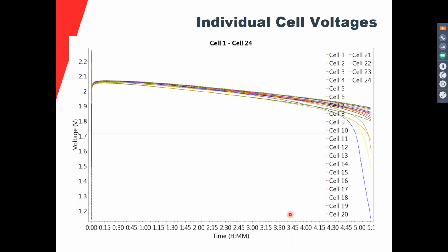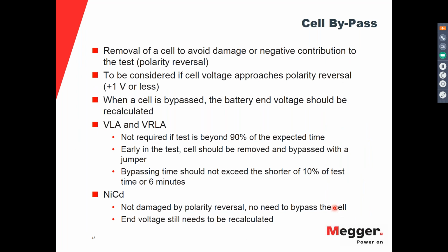And here we have another example, and this is a more critical example. You can see that there are three or four cells that are having serious issues, dropping the voltage very fast while the other ones still have very good voltage and very good capacity. So definitely it helps a lot to determine the condition of the cells. And it's actually critical to decide if you need to bypass a cell during the test. This is something that is allowed, and in some cases it is required.